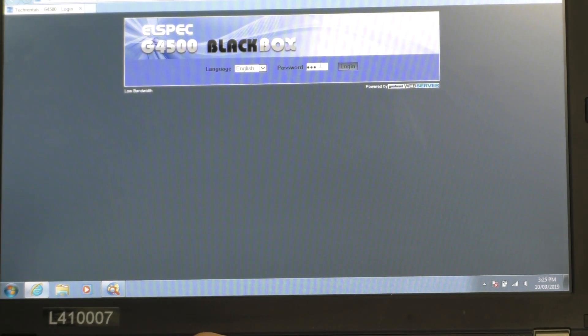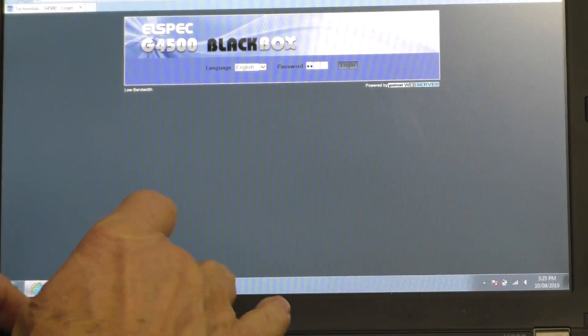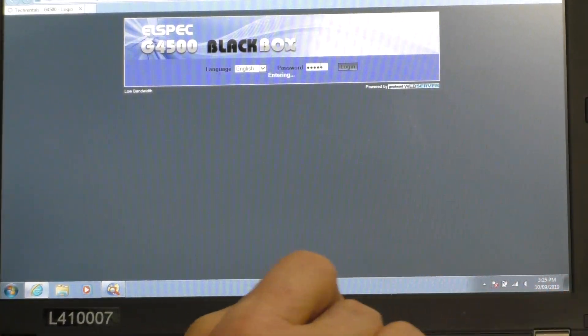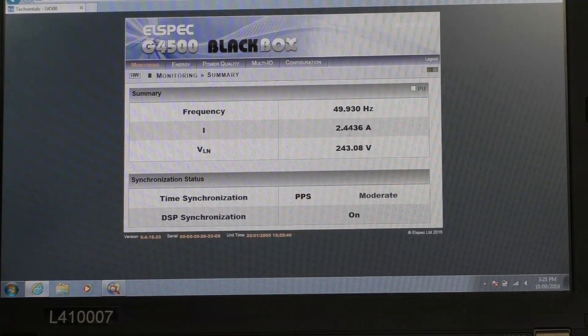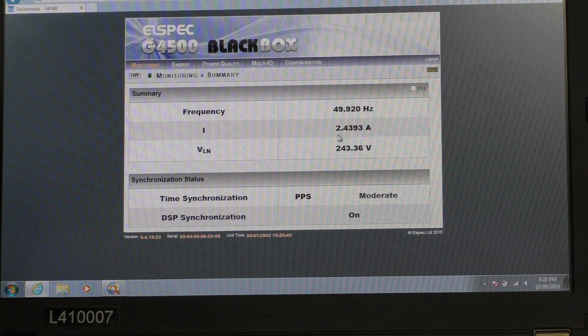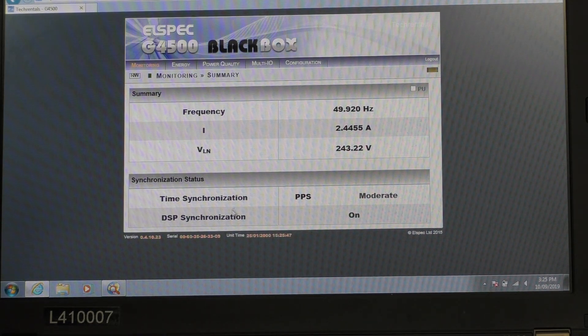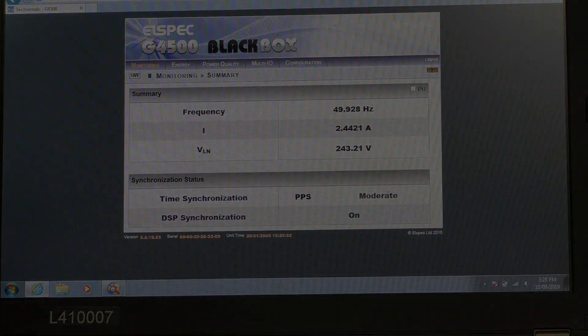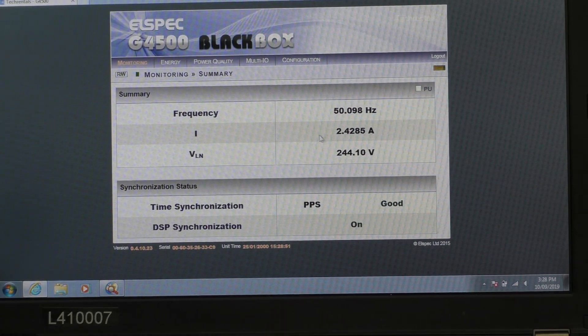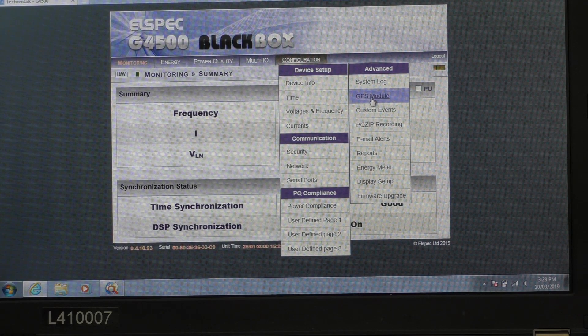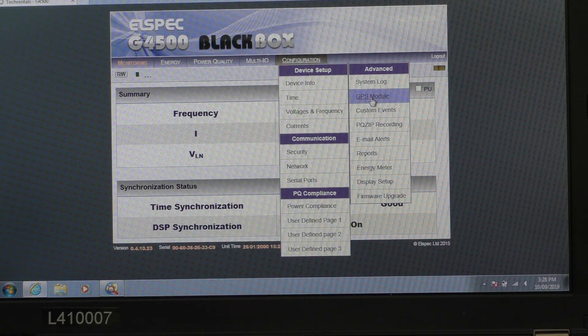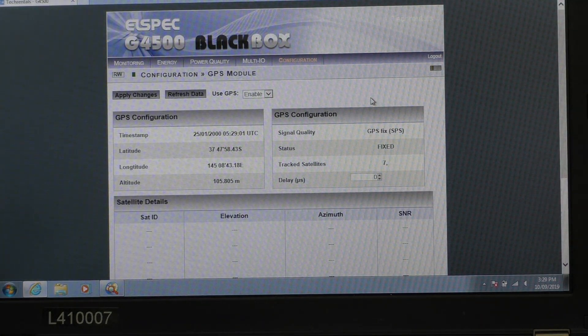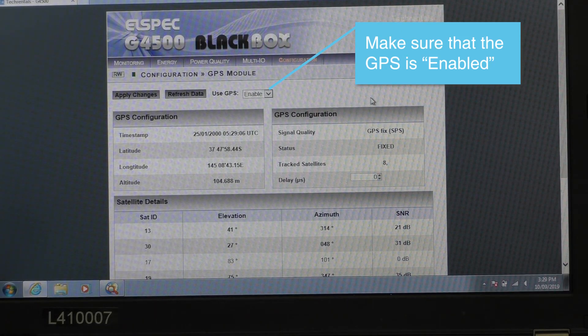The password is 12345, enter, now I've logged in. It initially comes up with a summary here with the frequency, the current and the voltage. We're doing single phase and the fact that we've got time synchronization from the GPS as well. Okay, we need to now configure the instrument. Under configuration here, device setup, we'll just check that the GPS module is all running happily. I'll click on that link and it comes up and it downloads. It's got a positional fix. So the GPS is working fine.